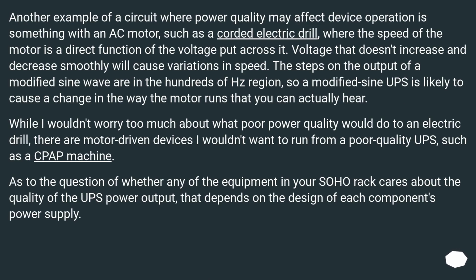Another example of a circuit where power quality may affect device operation is something with an AC motor, such as a corded electric drill, where the speed of the motor is a direct function of the voltage put across it. Voltage that doesn't increase and decrease smoothly will cause variations in speed. The steps on the output of a modified sine wave are in the hundreds of Hz region, so a modified sine UPS is likely to cause a change in the way the motor runs that you can actually hear. While I wouldn't worry too much about what poor power quality would do to an electric drill, there are motor-driven devices I wouldn't want to run from a poor quality UPS, such as a CPAP machine.